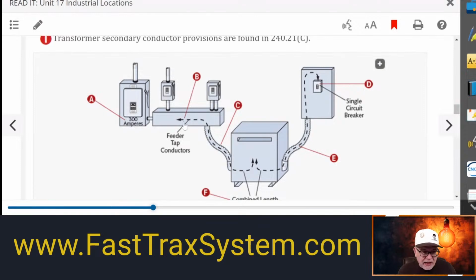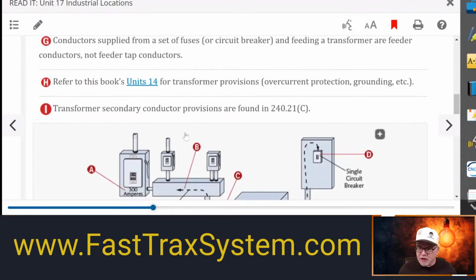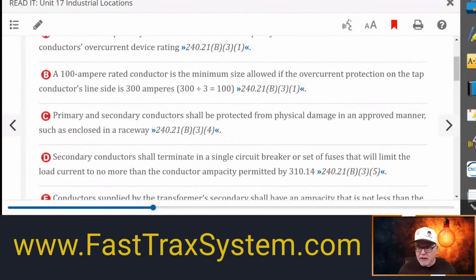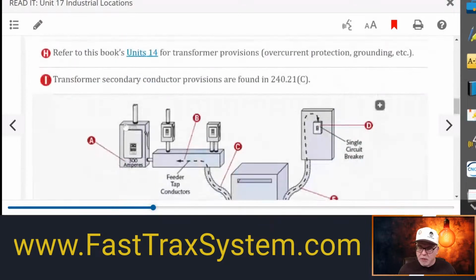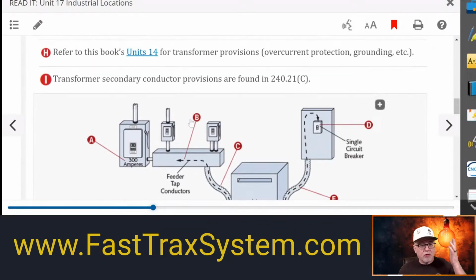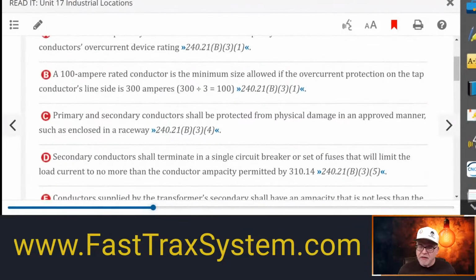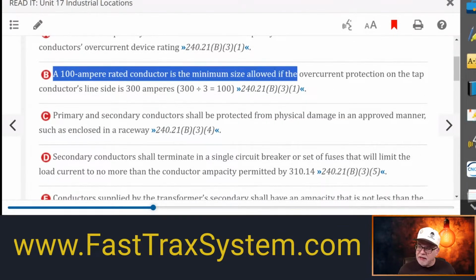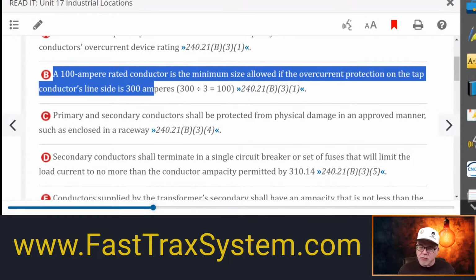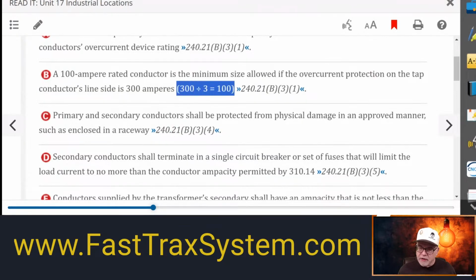to meet. So if we want to do this little tap dealy here, this is 300 amps. So first thing, we have to make sure that it can't be less. So this feeder tap right here, first of all, it cannot be less than 100 amps because that would be 1/3 of 300, right? So we already have our first factor that we have to consider. So no matter what we do, we know that this right here can't be less than 100 amps. And of course, if we look at our call outs, right, then we get that example right here, B, which is B right here. For those, again, those are in the fast tracks, are familiar with this. So B, it says a 100 amp rated conductor is the minimum size allowed if the overcurrent protection on the tap conductor side is 300 amps. Again, remember, it said 1/3.